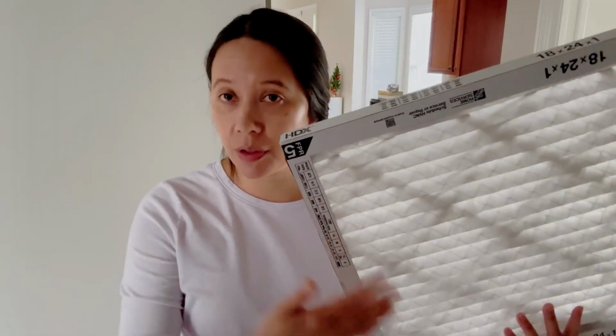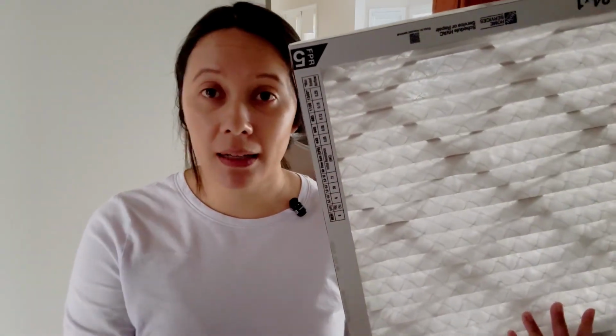Now you have your MERV 1 to 4, which is on the other side of the spectrum. I wouldn't worry about that. MERV 1 to 4 is basically like a large dust screen. You usually find them flat rather than pleated. Pleated is what you want because it increases the surface area, which means it's going to be able to catch more particles, whereas a non-pleated is not going to be able to catch as many.